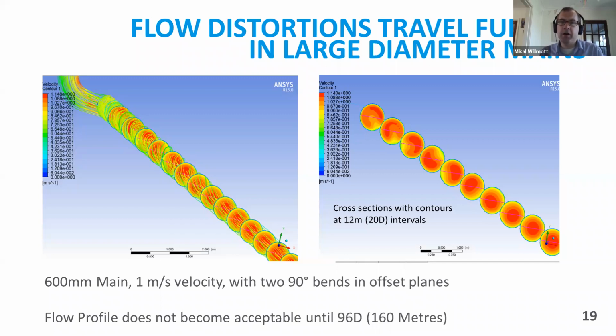And what Andy showed right at the start was that an ideal profile is where you have fast water in the middle, and then gradually, in a very symmetrical way, you get lower and lower velocities. And when you go through a bend or through fittings, the flow profile can get distorted. The effects of a disturbance dissipate quicker, we believe, in a smaller pipe. This is probably due to the ratio between the pipe diameter and the area within a pipe. For larger pipes, the ratio between the area within the pipe and the pipe diameter is greater. So in a small pipe, if you're a molecule of water, as you come round a bend or go past a fitting, you may very quickly hit the sides of the pipe.